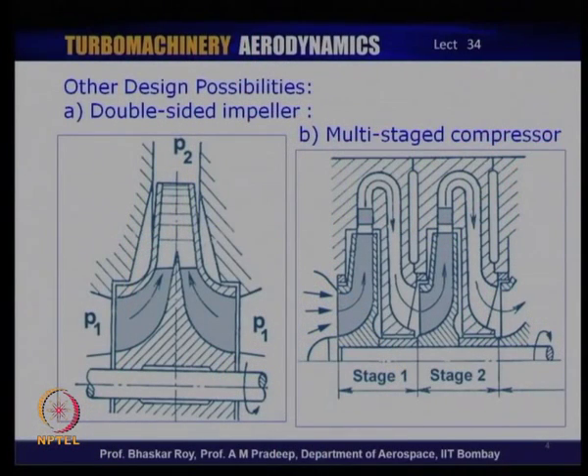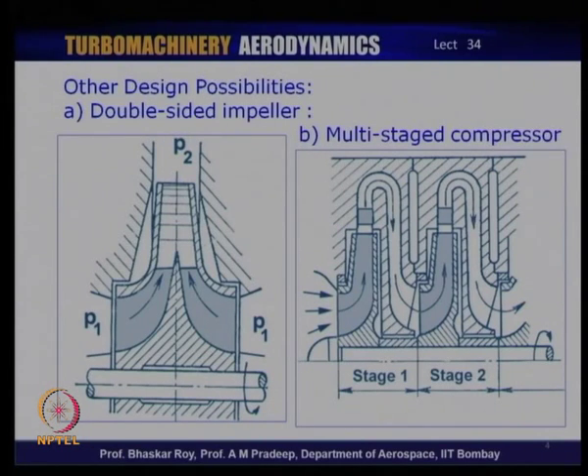There are a couple of varieties of centrifugal compressor that you may need to decide upon at the beginning of the design. One of them is the double-sided impeller, in which flow is brought into the centrifugal compressor from two sides. This is essentially done to increase the mass flow through the centrifugal compressor, since mass flow is somewhat restricted by its inlet which is smaller than its outer diameter. By allowing flow to come from two sides, you are almost doubling the mass flow, and then the compression is done over the two mass flows together through one centrifugal impeller.